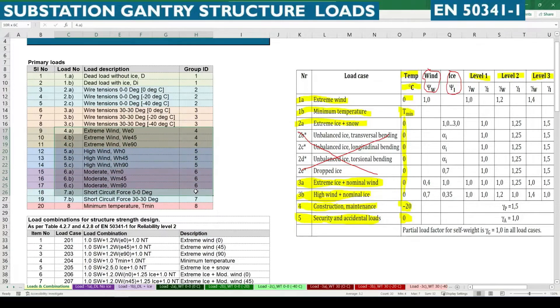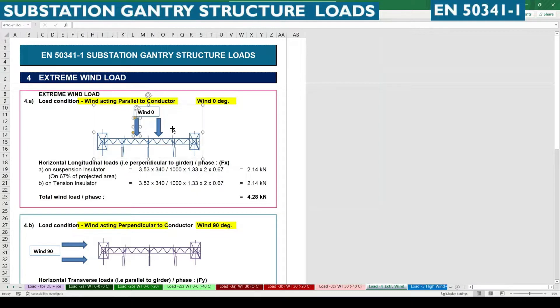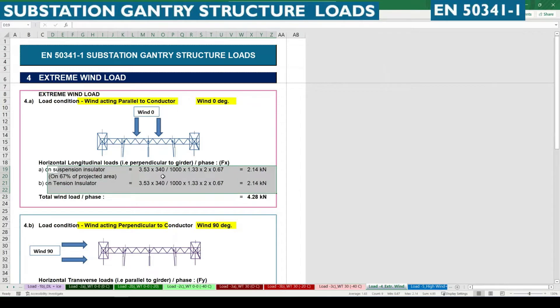For the extreme wind cases, this is the extreme wind case sheet in which we are going to calculate the load acting at zero degree angle — that means acting parallel to the conductor. As you can see in this image, the wind force direction is acting parallel to the conductor span. When wind acts parallel, there won't be any wind force due to the conductor — only wind forces due to the suspension insulator and tension insulator are applicable.